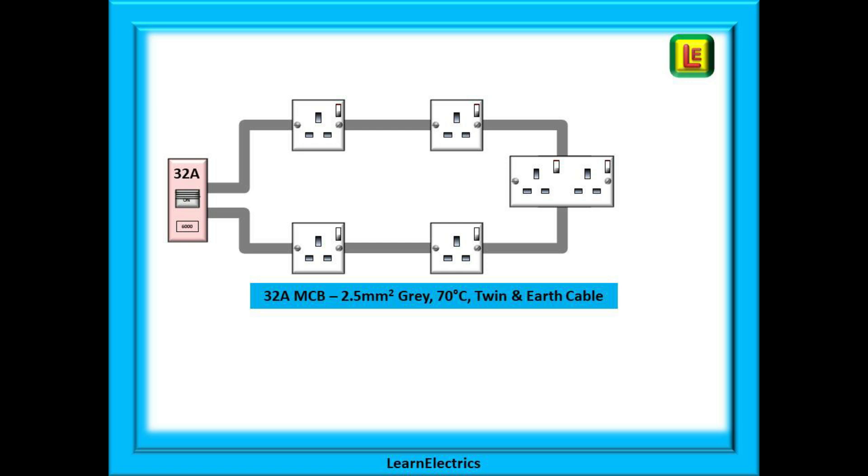This will be perfect for us to understand voltage drop and circuit length calculations in these circuits. We've included a double socket to visually mark the midpoint for our calculations today, but in reality any combination of singles and doubles is acceptable. We are going to keep things standard, so it is protected by the usual 32 amp circuit breaker and wired in 2.5 millimeter twin and earth cable.